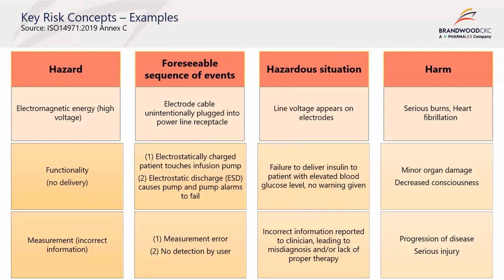The electrostatic discharge causes the pump and pump alarms to fail. The hazardous situation occurs where there is a failure to deliver insulin to the patient with an elevated blood glucose level, and no warning is given. The harm to the patient is minor organ damage or decreased consciousness.